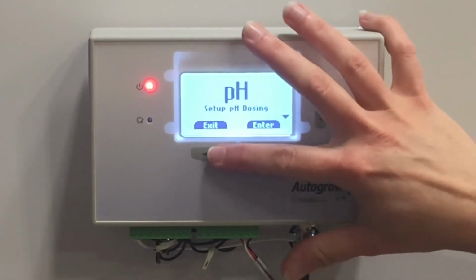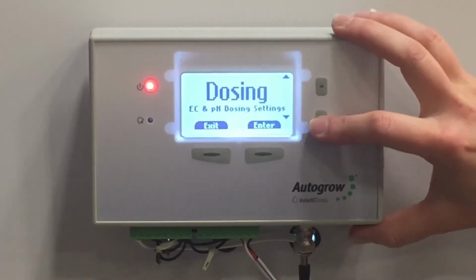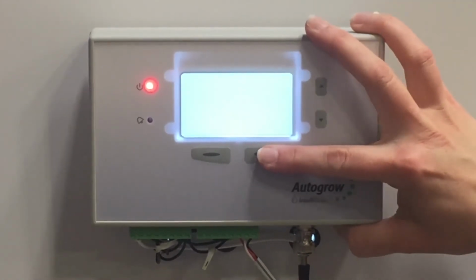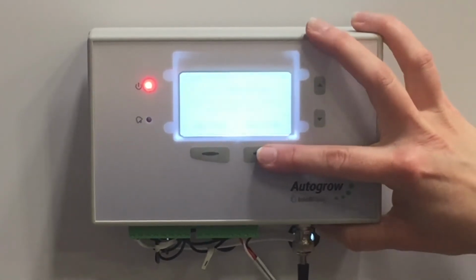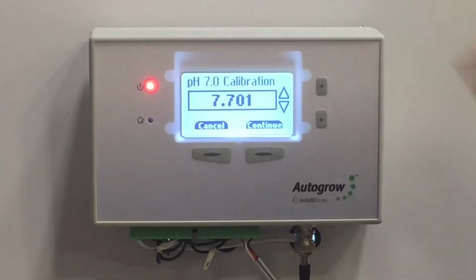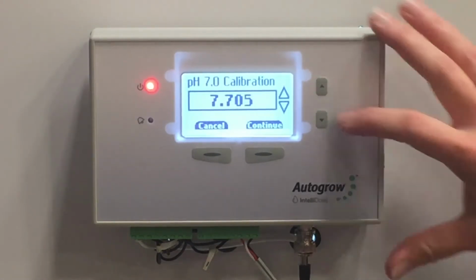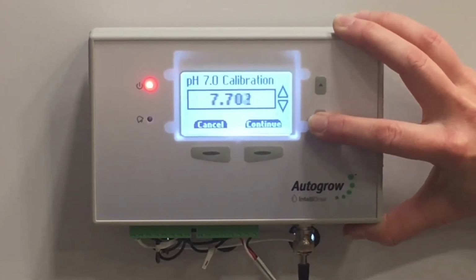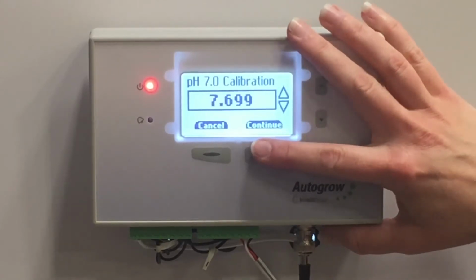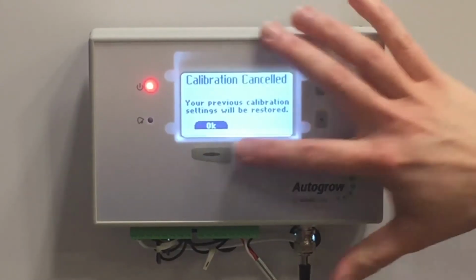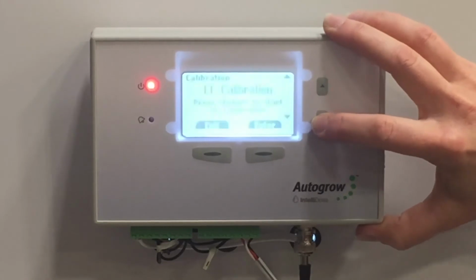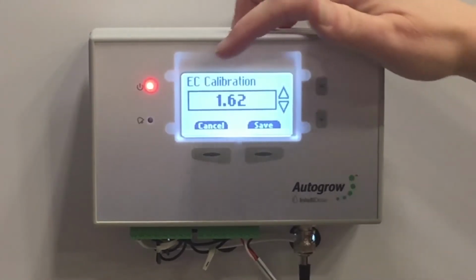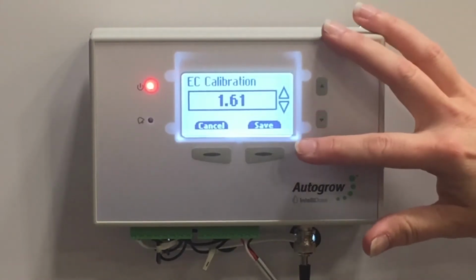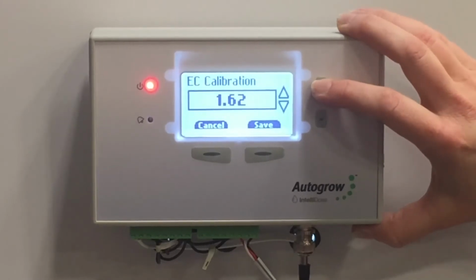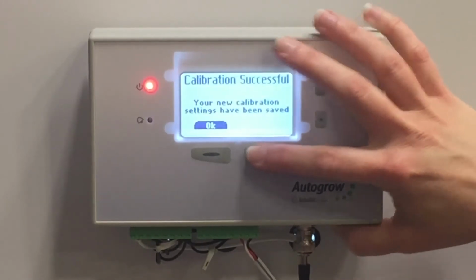Calibration is super easy on the IntelliDose. You simply go to the calibration screen, hit enter, you go into pH calibration, and you'll see it says pH 7.0 calibration. Set your probe in 7.0 solution, dial it in, using the arrows, and when you get to 7.0, hit continue. To calibrate your EC, hit enter, put it into the 2.77 solution, use your arrows to get it correct, and then hit save.